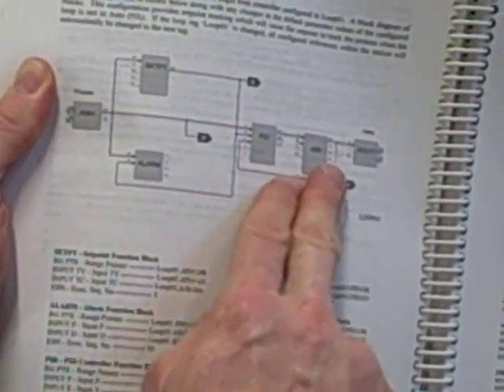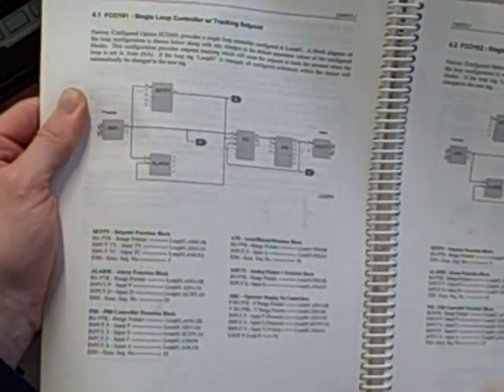This controller uses function block style programming to determine how it's going to react. Factory Configure Option 101 defines these function blocks: analog input, set point, alarm, PID, auto manual, and analog output, describing how the information flows through the controller.